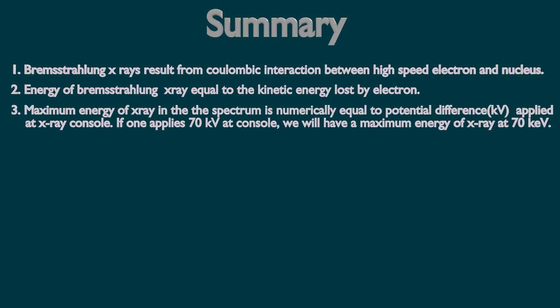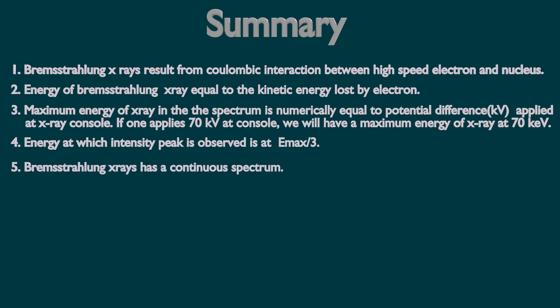If one applies 70 kV at console, we will have a maximum possible energy of X-ray at 70 keV. Energy at which intensity peak is observed is maximum energy divided by 3. Bremsstrahlung X-rays have a continuous spectrum.